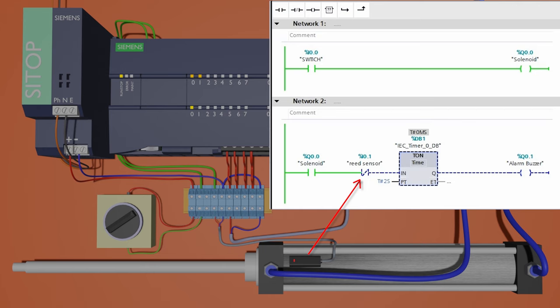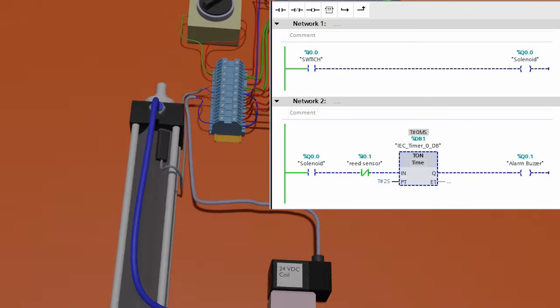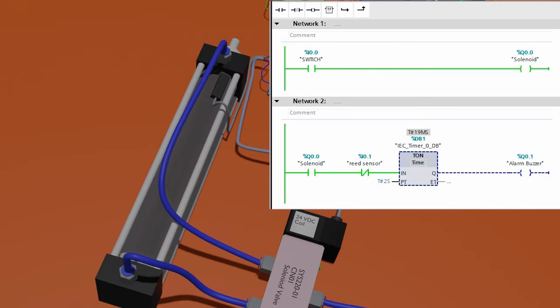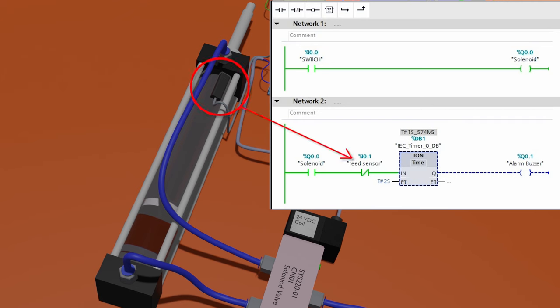Now let's see a scenario where the cylinder malfunctions. As we turn the switch on, it will activate the solenoid Q0.0 and the solenoid supplies the compressed air to the cylinder, and the cylinder shaft starts to move outward. But halfway through, the cylinder shaft sticks and the shaft piston cannot reach the reed switch. The normally closed contact I0.1 of the reed switch remains closed and the safety timer continues. Once the two seconds are over, the timer will activate the buzzer to alert the machine operator to take corrective action.